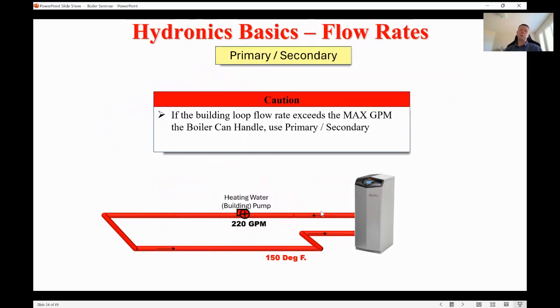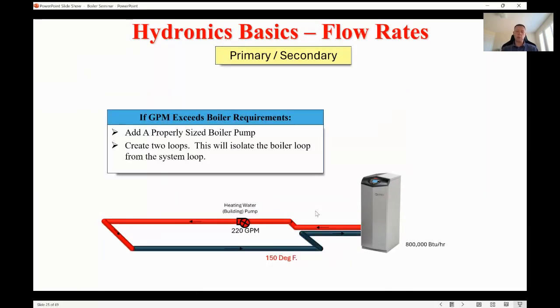Really, low mass boilers used to be, there was all high mass boilers, steel tube, cast iron sectional, way back in the day. And how primary, secondary really came to be was, way back when, somebody started importing copper tube boilers. And everything here, they'd have one pump on the system. They're used to putting in a cast iron or something. They started putting these low mass boilers in. What they found is there's a lot of failures because that low mass product couldn't handle these high flow rates. So one of the pump manufacturers saw that this was a big issue and decided to tackle it. And what they did, I'm sure after quite a bit of testing, was they realized that if they completed that secondary loop, that system loop, created those two T's there, I'm sure they messed around with how far apart they could be to achieve that hydraulic separation, put those in, put a pump that's designed to give the boiler exactly what it needs, it alleviated all these problems. So this is primary, secondary piping. The boiler basically is hydraulically separated. It gets the flow it needs, and the building is getting the flow it needs. And the genius of this for the pump manufacturer is now they're selling 2 pumps on this job instead of 1.